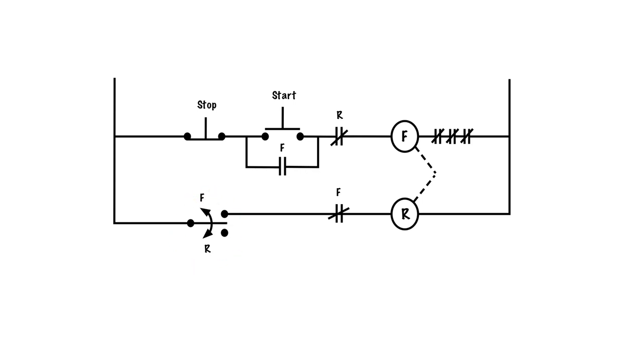And the motor is completely stopped and the centrifugal switch is now in its normal position, sitting between the forward and the reverse. And so that is how you use a zero speed switch which is attached to the shaft of the motor to plug a motor to stop.